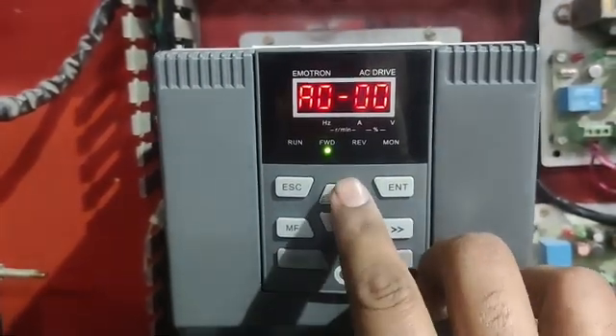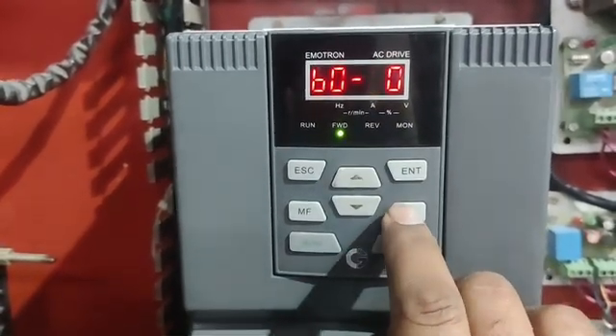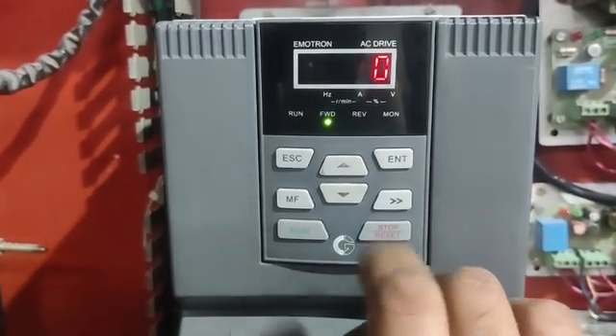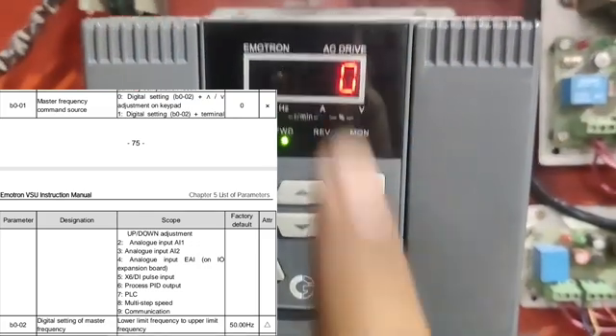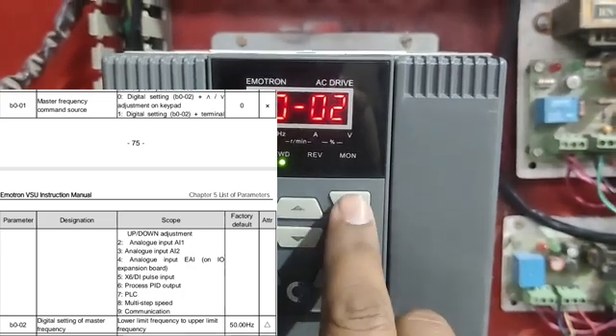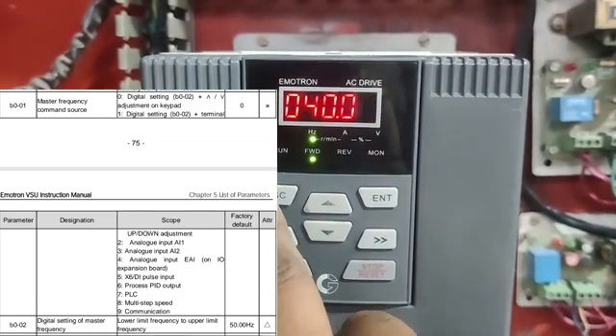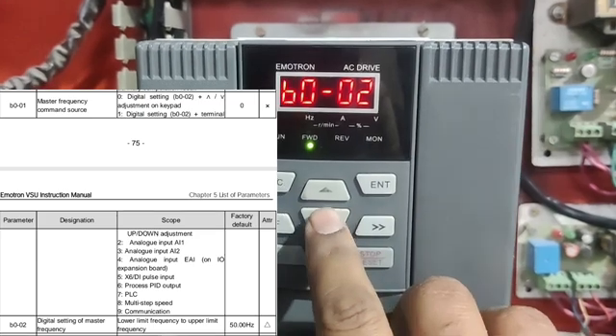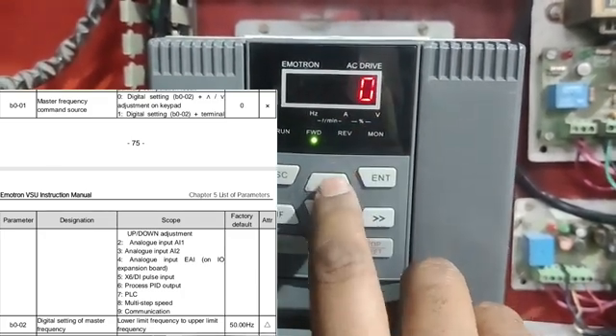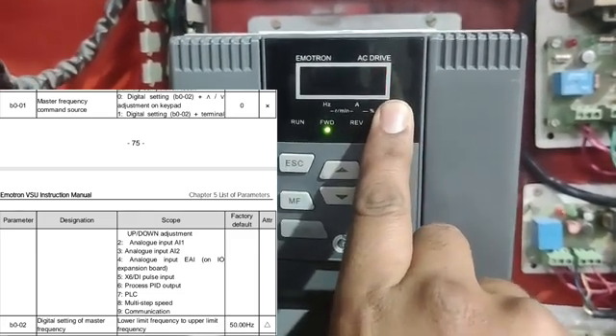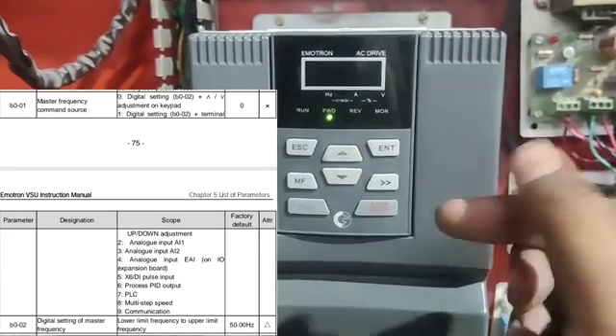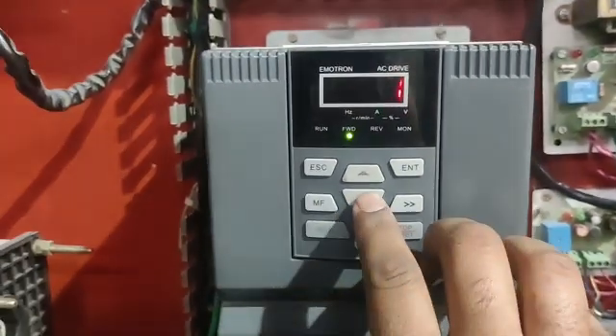For parameter setting, first press Enter, go to A0-00, then press Shift to reach b0-00. We need parameter b0-01, which is Master Frequency Command Source. We set zero for keypad mode — frequency will increase or decrease as set in keypad mode. If we set one, then terminal up/down adjustment allows frequency increase or decrease with a push button. If we set two, frequency will increase or decrease with a potentiometer.